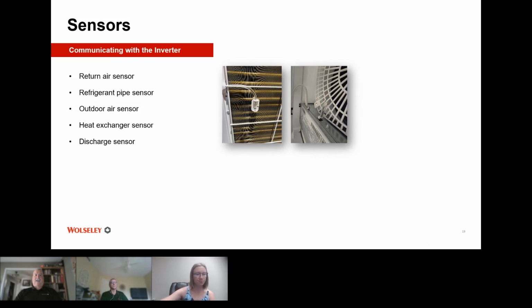Thanks, Michael. Now, the sensors that are commonly associated with inverter technology, which most major brand manufacturers of heat pumps use today, encompass five different kinds of sensors. We have a return air sensor. We have a refrigerant pipe sensor. We have an outdoor air sensor, and we have a heat exchanger sensor and a discharge sensor. All of these sensors are in essence sending information to the board of the outdoor unit, and the unit is using its algorithm to make that unit run as efficiently and economically as it can, depending upon demand and set point.